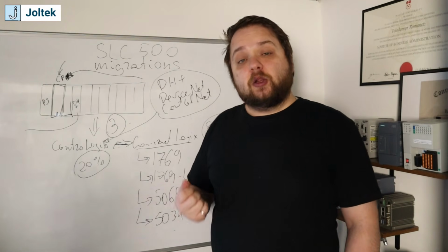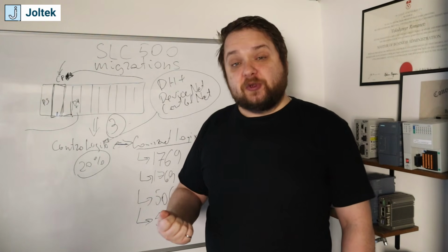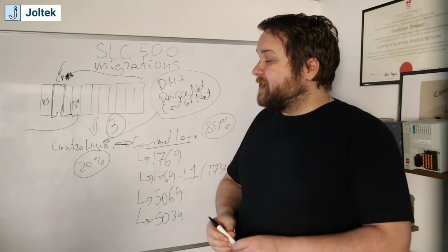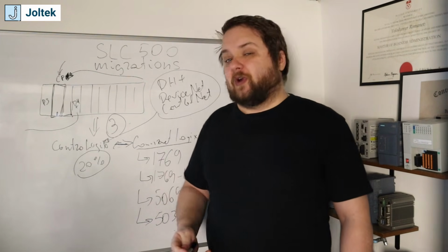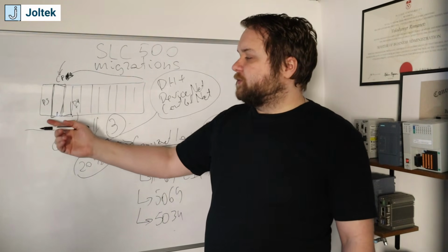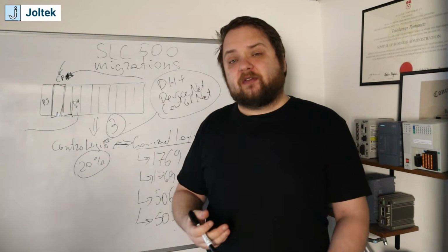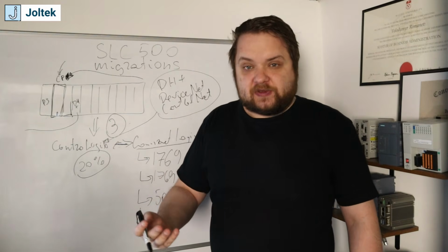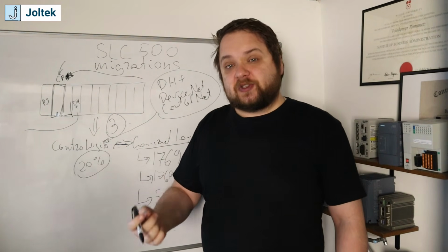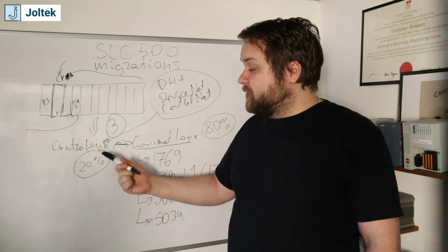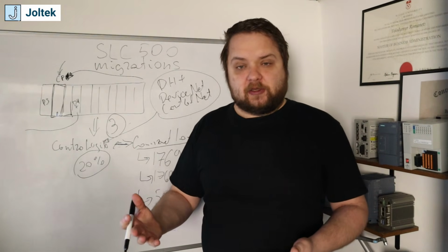Number three, a lot of the manufacturers are looking to better connect to their systems, and as part of that initiative, you can usually justify a certain number of upgrades. So remember, of course, if you're talking to this rack over Data Highway Plus, you will struggle to extract the information that you need in certain instances. There's usually going to be a much lower limit of connections from these racks as opposed to the more modern implementations on ControlLogix and CompactLogix.